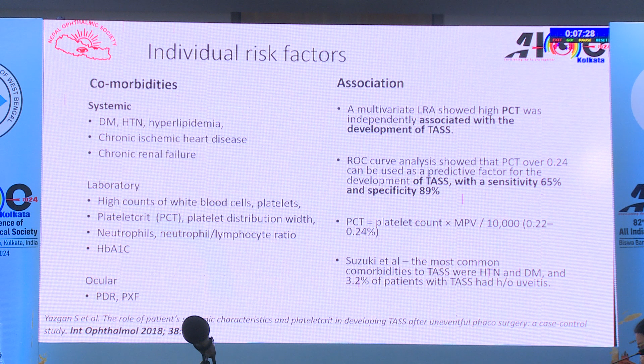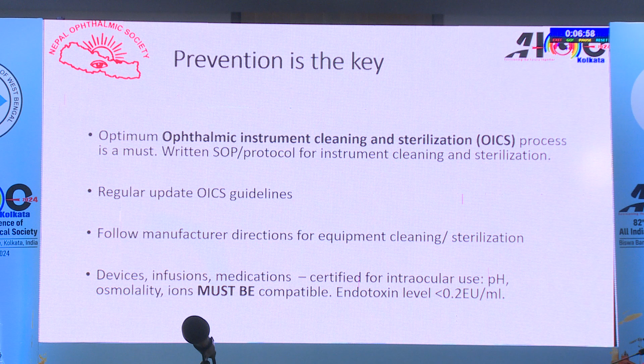So prevention of TASS is the key. An optimum ophthalmic instrument cleaning and sterilization process is a must. There should be a written SOP, a protocol for instrument cleaning and sterilization, with regular updates of the sterilization guidelines. We should follow the manufacturer's directions for equipment cleaning and sterilization, and use devices, infusions and medications certified for intraocular use. We should always check pH, osmolarity and ions, and they must be compatible. Endotoxin level should be less than 0.2.